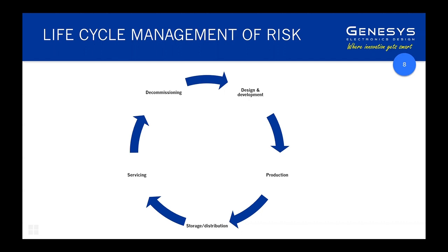So the path of least resistance in terms of getting FDA approval, for example, is to follow the risk management as per the technical reports, even though they're not mandated by the standards. So ignore those technical reports at your peril, and I'll be talking to them during the course of the presentation. So what's your experience of the range of different companies that you've worked in? Do they all look a little bit different, or are they the same?